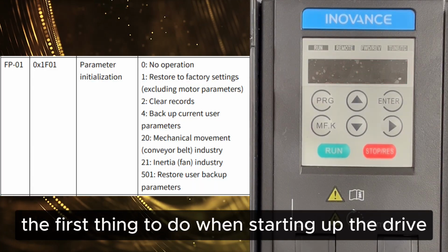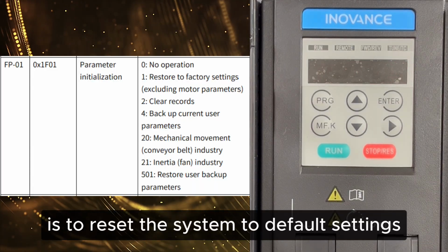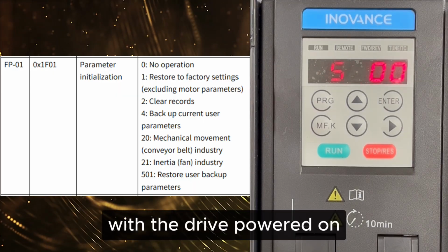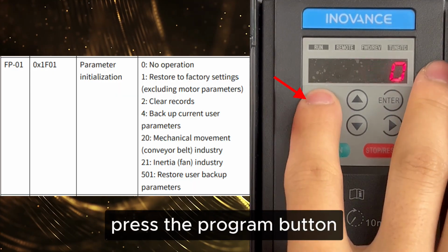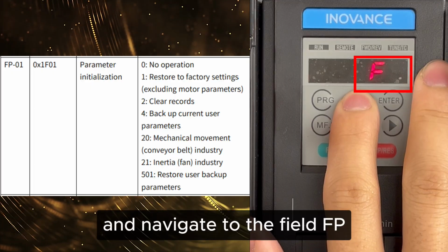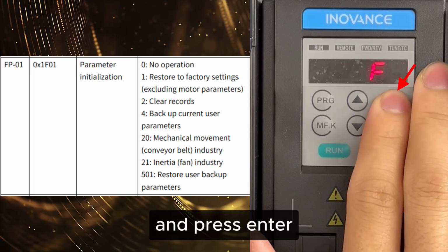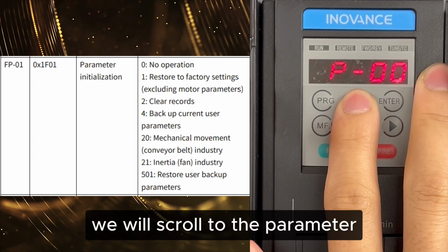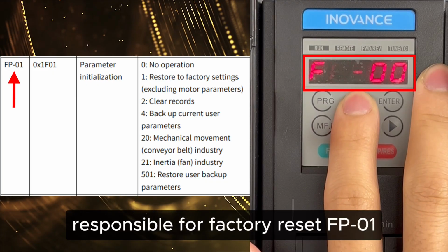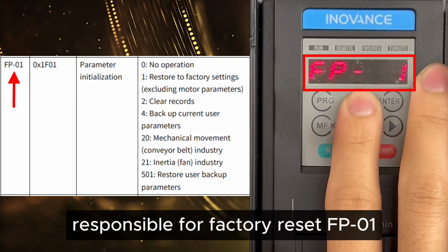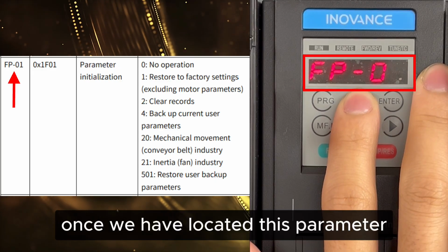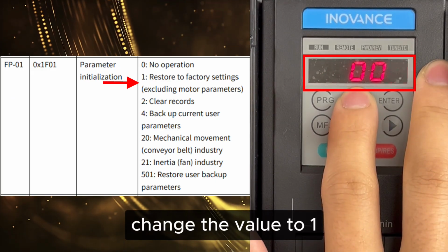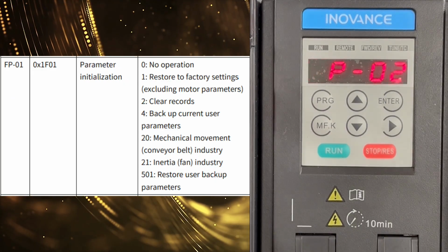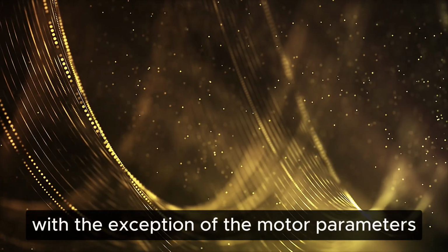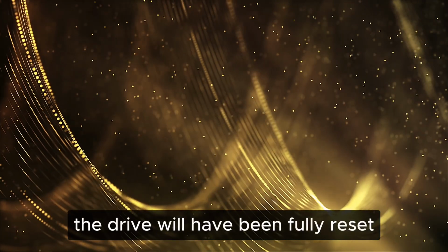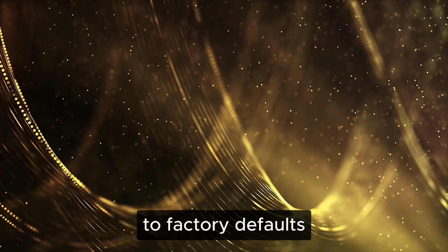The first thing to do when starting up the drive is to reset the system to default settings. With the drive powered on, press the Program button to enter the parameter menu and navigate to the field FP, and press Enter. We will scroll to the parameter responsible for factory reset, FP-01. Once we have located this parameter, change the value to 1, then press Enter to confirm. After a moment, with the exception of the motor parameters, the drive will have been fully reset to factory defaults.